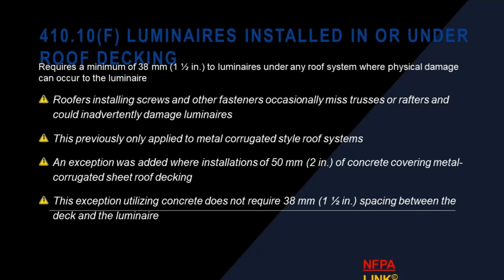Okay, 410.10(F), luminaires installed in or under roof decking. It requires 38 millimeters, or 1.5 inches, to luminaires under any roof system where physical damage can occur to the luminaire. So roofers installing screws and other fasteners occasionally miss trusses and rafters and could inadvertently damage luminaires. So now, if we are going to be putting lights in under roof decking, we have to have 1.5 inches. Okay, so on our commercial tenant finishes, when we slap those lights up there, they need to be 1.5 inches down below the roof decking. The exception, though, is that utilizing concrete does not require the 1.5 inch space.